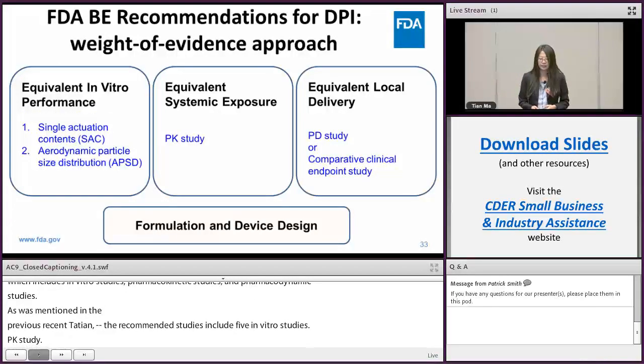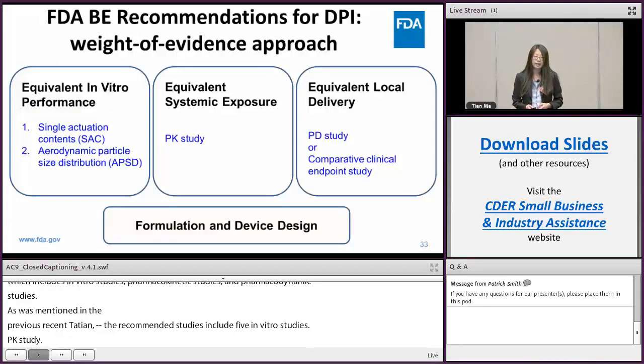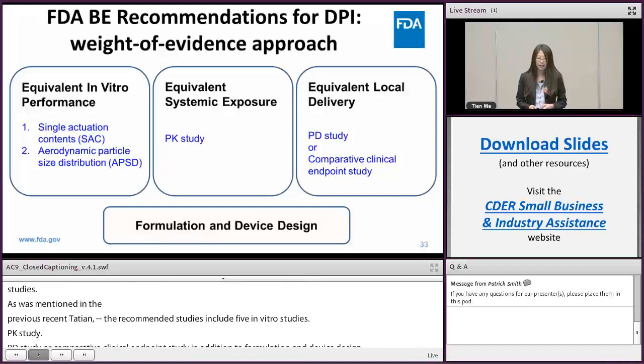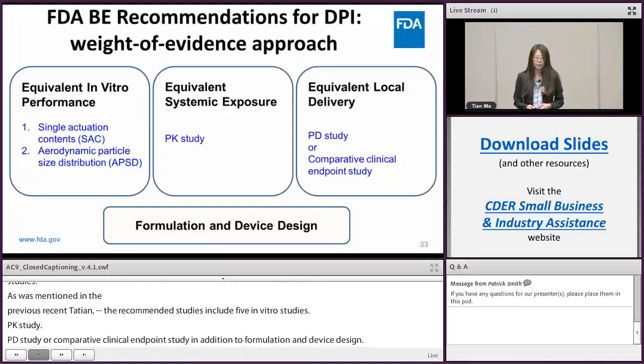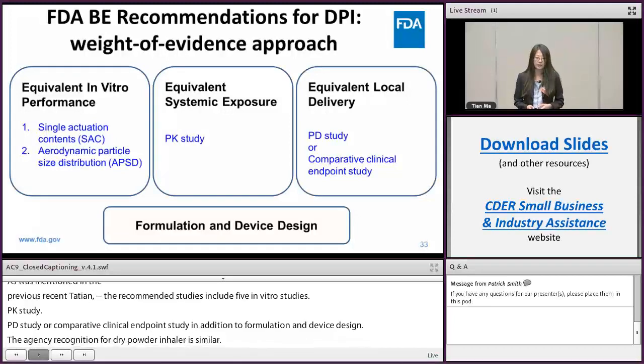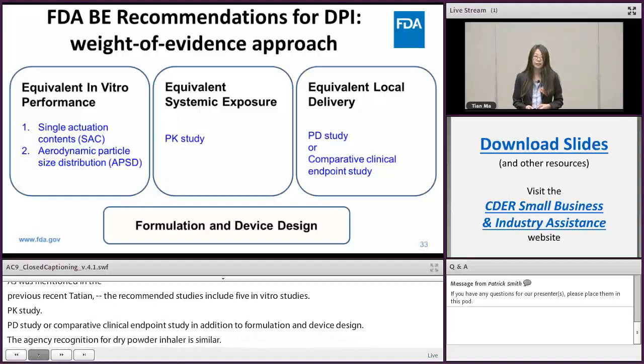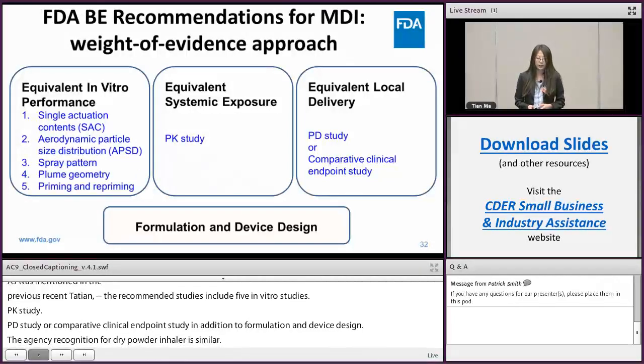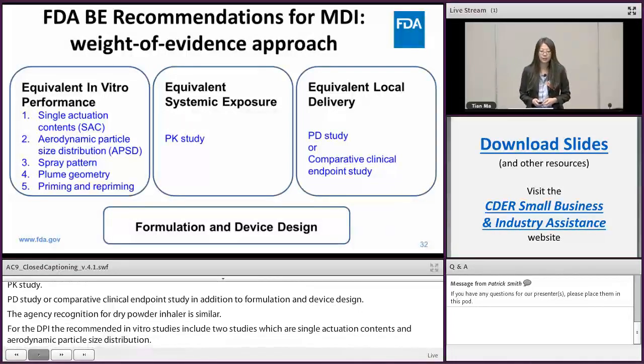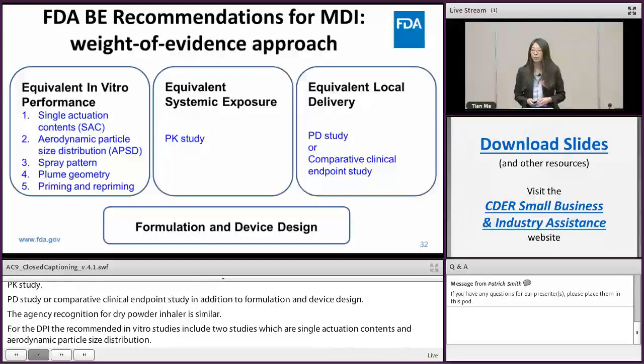The agency's BE recommendation for the dry powder inhaler is similar to that for the MDIs. Please note that for the DPI, the recommended in-vitro studies include two studies: single actuation content (SAC) and aerodynamic particle size distribution (APSD). Whereas for MDI products, in addition to SAC and APSD studies, spray pattern, plume geometry, and priming and repriming studies are also recommended.